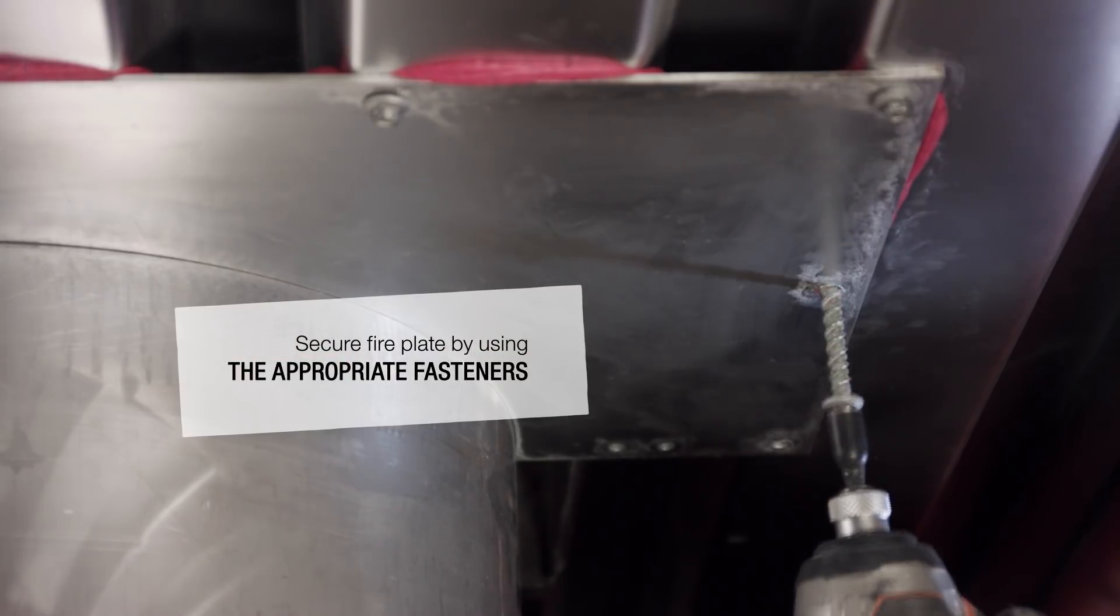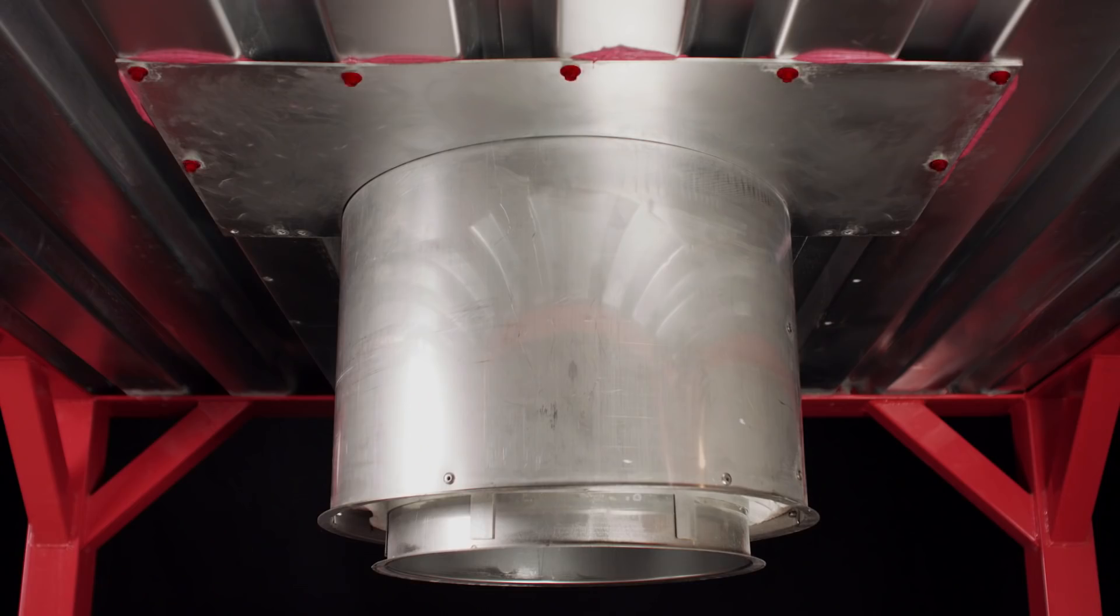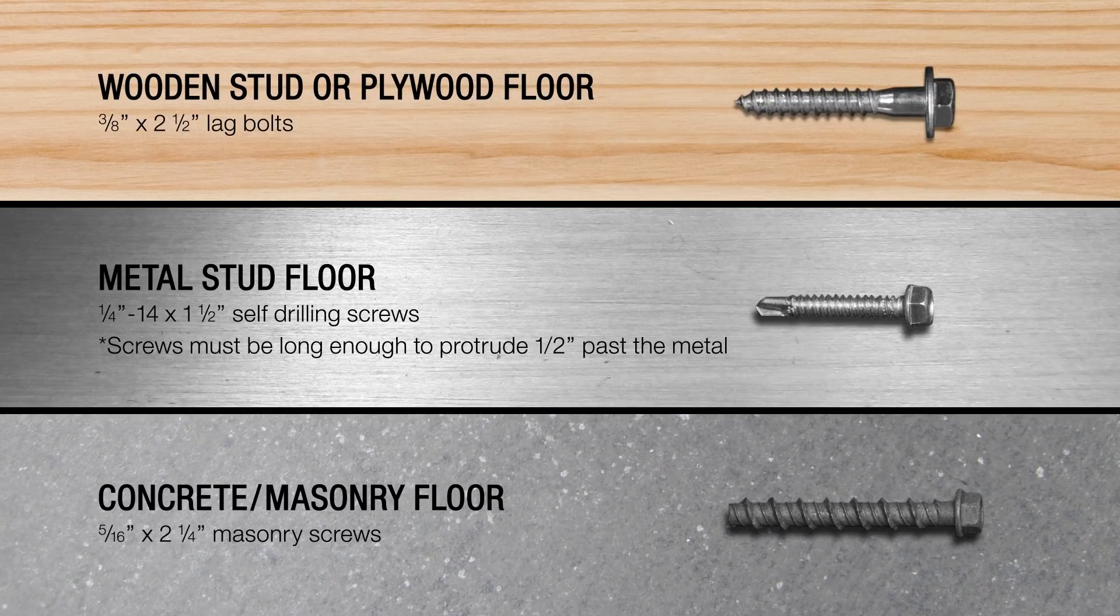Secure the plate to the underside of the floor using the specified fasteners for your floor or ceiling type along the outside edge of the plate. Do not install hardware along the bottom edge of the fire plate. All screws for each floor or ceiling type can be provided by the project contractor or included as an option.